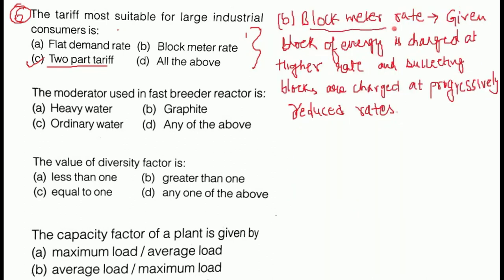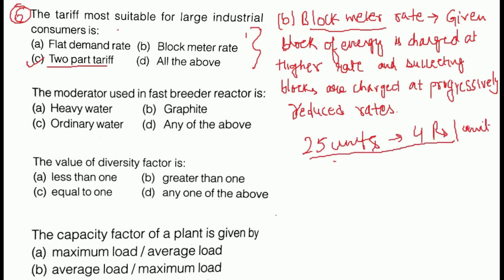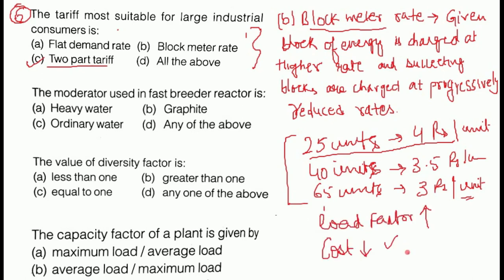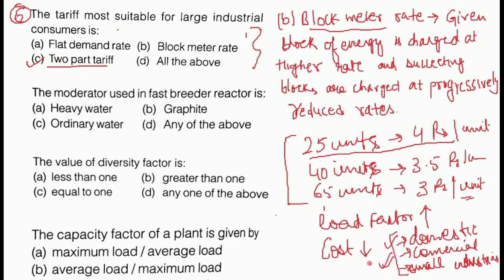Next method is the block meter rate method. In this method, the starting units are charged at a higher rate and then subsequent units are charged at progressively lower rates. For example, the first 25 units at 4 rupees per unit, next 40 units at 3.5 rupees per unit, and next 65 units at 3 rupees per unit. This method encourages the consumer to consume more units, which increases the plant's load factor and reduces generation cost. This method is used for domestic, commercial, and small industries.